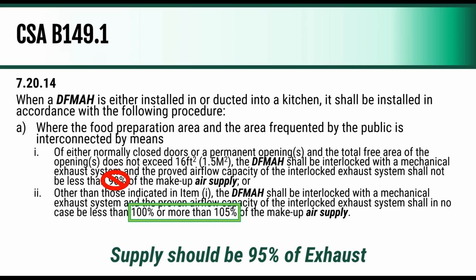To touch quickly on that, the difference between direct fired and indirect fired. Direct fired makeup air units have a burner directly into the airstream, so you have products of combustion that are part of that airstream that are going into the kitchen, which is why they are more tightly regulated, i.e. you need to be exhausting most of that out rather than pushing it into the space. Indirect units don't have an exposed flame or burner in the airstream, so they're heating in a different chamber and then transferring that heat into the airstream, typically through a heat exchanger, or sometimes you're using steam from a building steam system or cooling from a building cooling system. That allows you to almost do whatever you want with supply versus exhaust ratios. But again, you do need to have a negative kitchen.